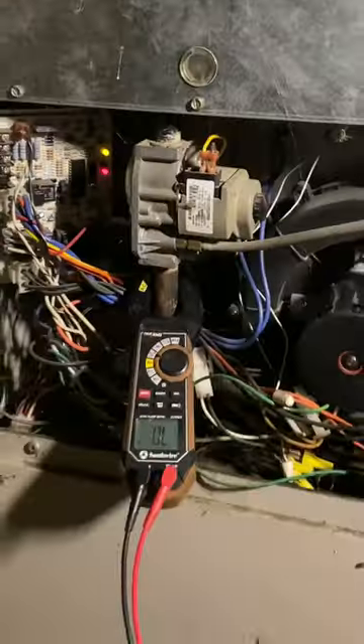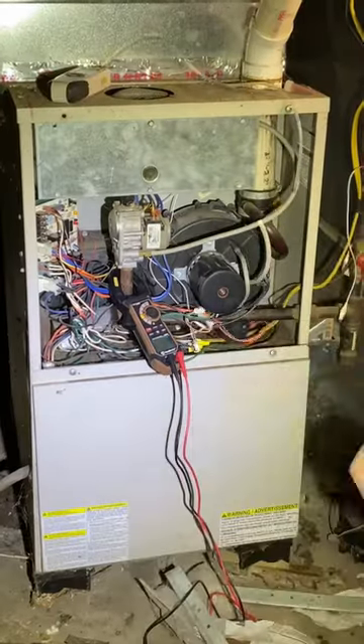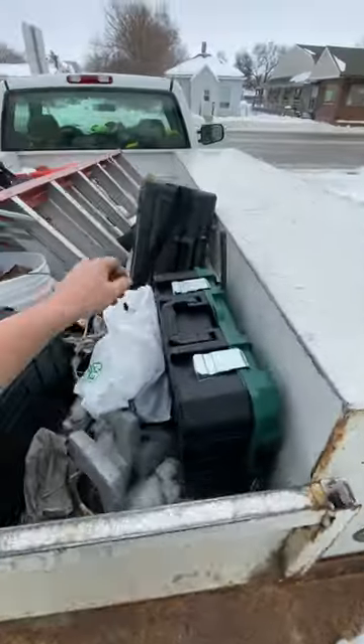Get on site, power cycle the furnace and start the diagnosis process. What we're going to do is check the vent outside. That being open, we're going to head inside and jump out the safety and test it with a manometer.